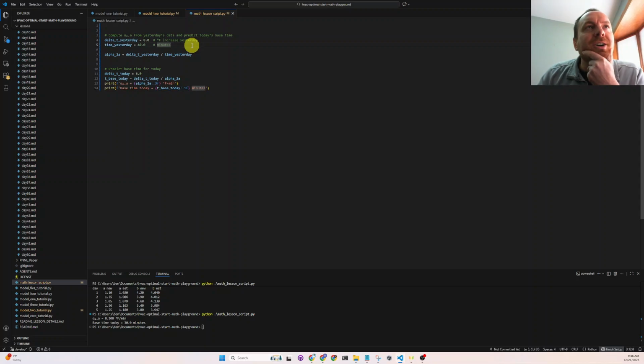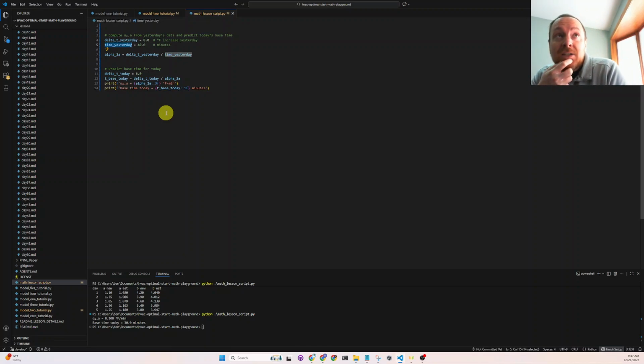So we just kind of pretend that maybe perhaps 2 hours before the building started up, our zone temperature got colder because the HVAC is off. So we're a cold building, 8 degrees below our occupied heating set point. So that's what that is. And then this would be yesterday's actual warm-up time performance. So that would be where our algorithm captured 40 minutes.